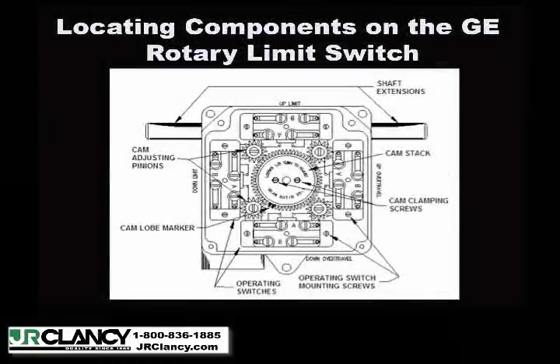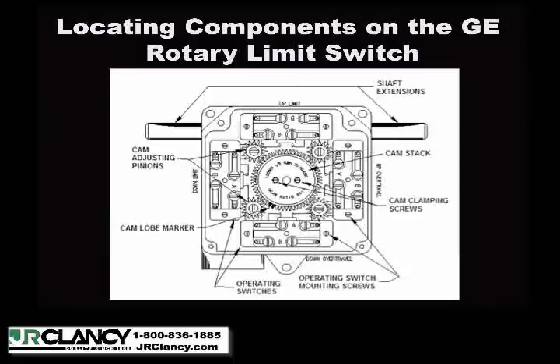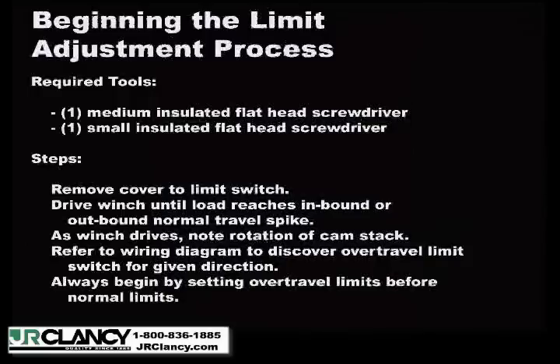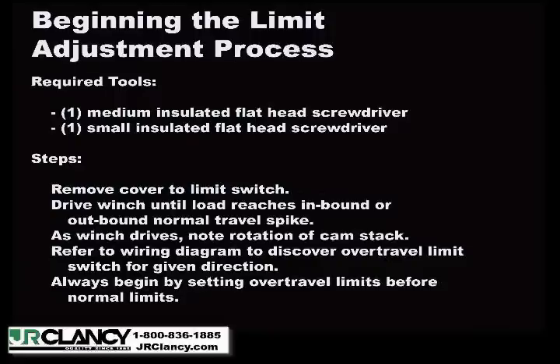This graphic is a map locating components on the GE Rotary Limit Switch, available in PDF format from the J.R. Clancy website. To begin the limit adjustment process, we will need several required tools: one medium insulated flathead screwdriver and one small insulated flathead screwdriver. Care should be taken to avoid the contacts on the switch as they are live and carry control voltage.